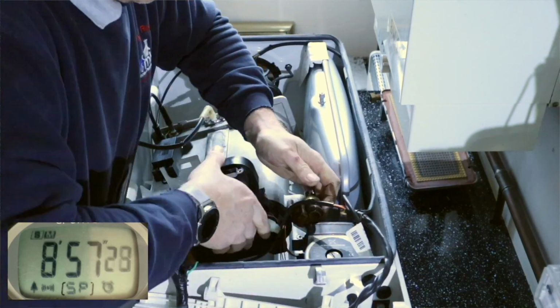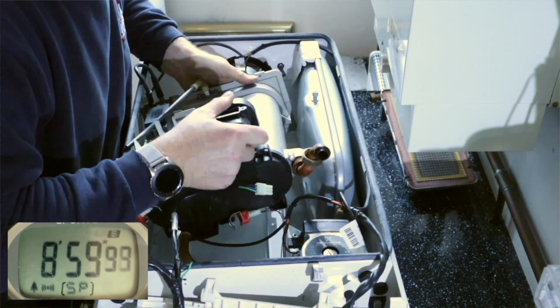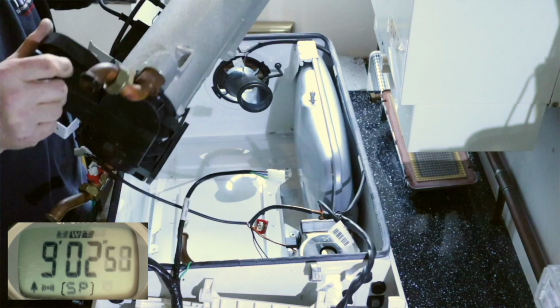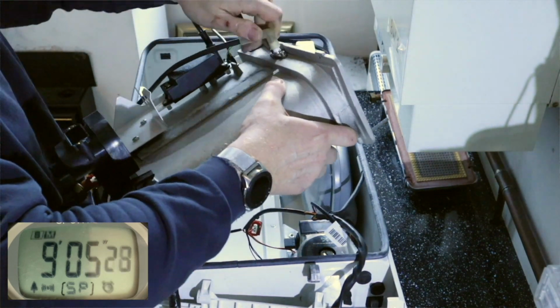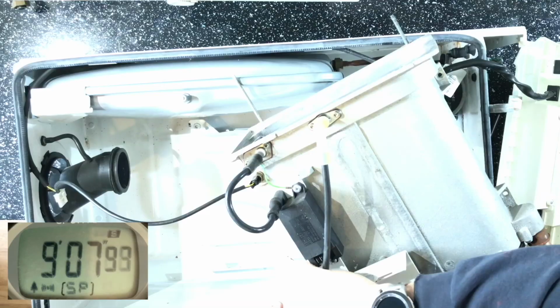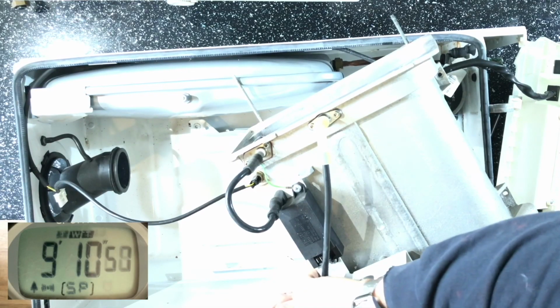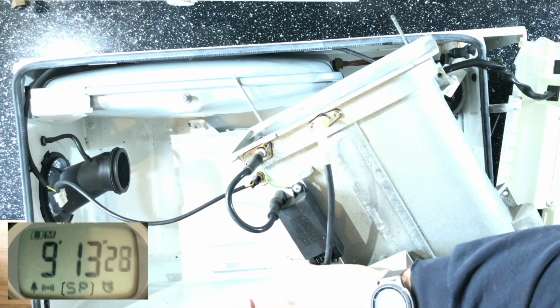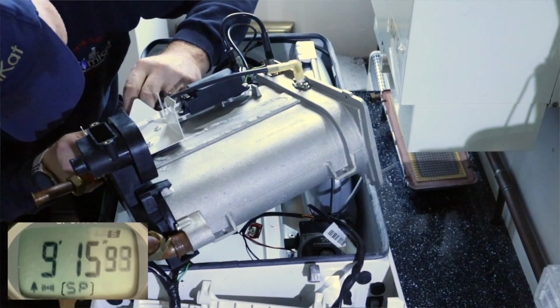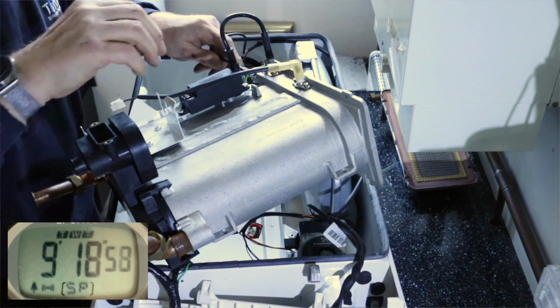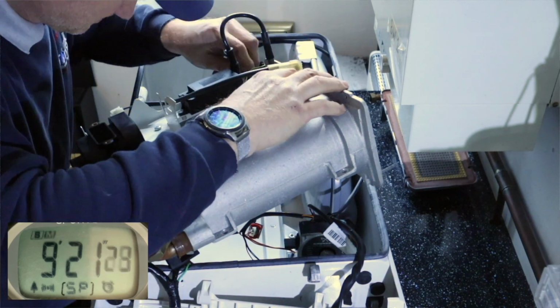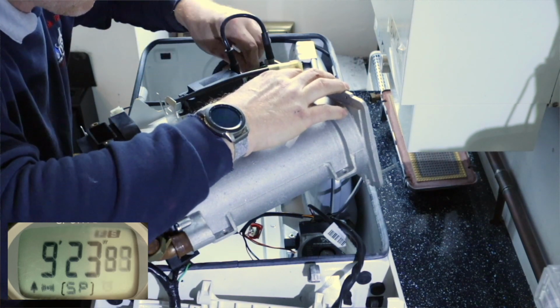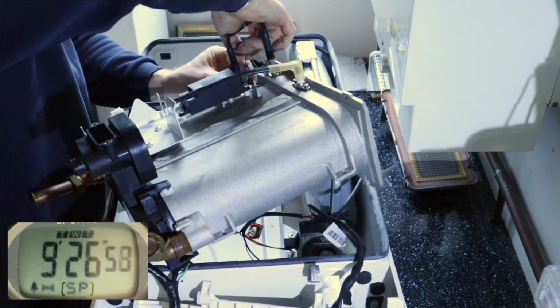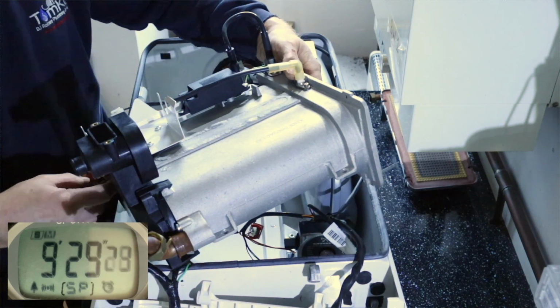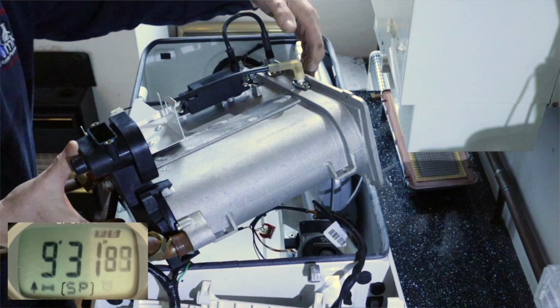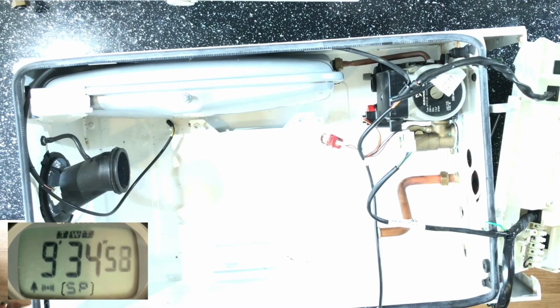Now I've undone this nut on top of the pump, I can now take the primary heat exchanger out, so it comes out as one complete unit. So first of all I'm just going to disconnect the flame rectification lead. There's like a little plastic junction box there to allow me to disconnect it finally. And now I'm just taking off the wire going to the no flow sensor, on this top left hand side of the heat exchanger, and now I'm just taking off the thermistor cable on the flow thermistor. So that's all out now.